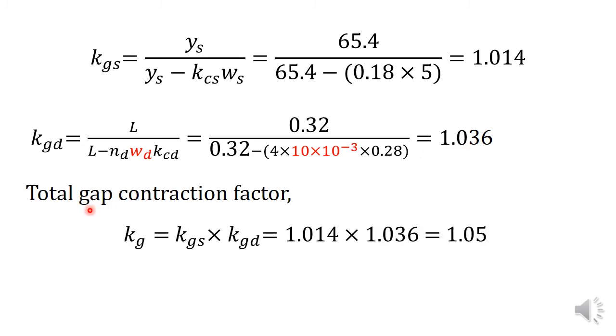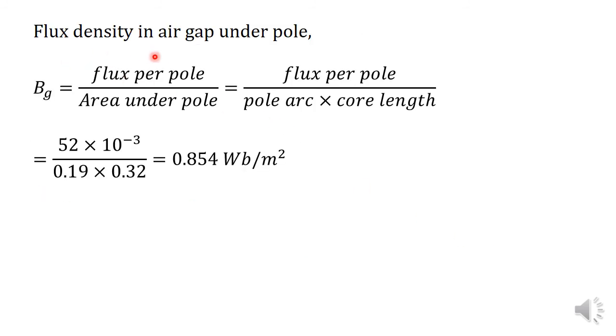The total gap contraction factor for slots and ducts is KGS into KGD, equal to 1.05. The flux density in the air gap under the pole, BG, is equal to flux per pole divided by area under pole (pole arc into core length). That is 52 × 10⁻³ divided by (0.19 × 0.32), which equals 0.854 weber per meter square.